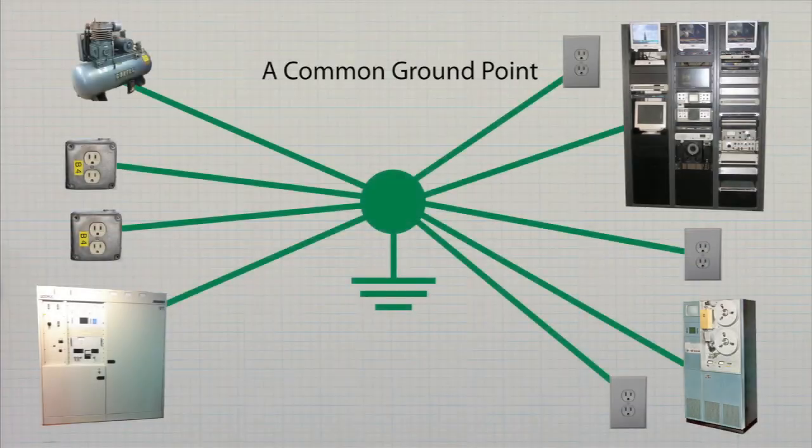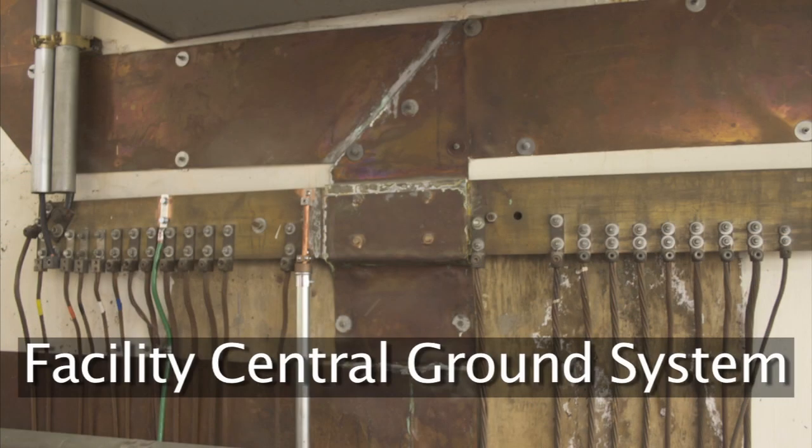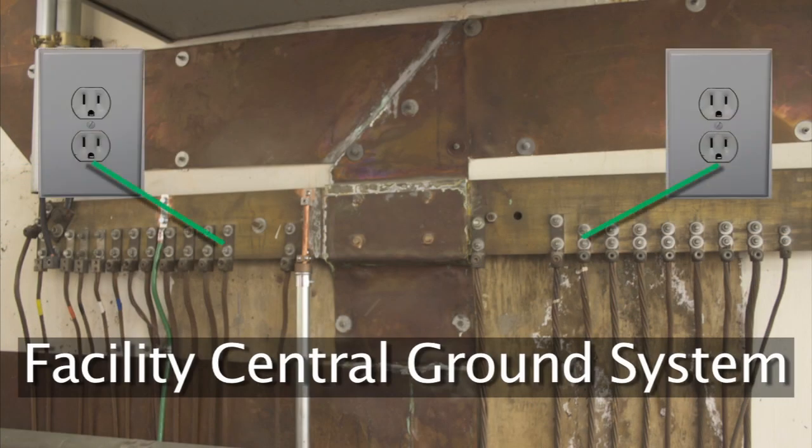The best way to prevent ground loops is by using a centralized grounding system in your facility. All grounds are connected to a single point that has a very low resistance to earth ground.